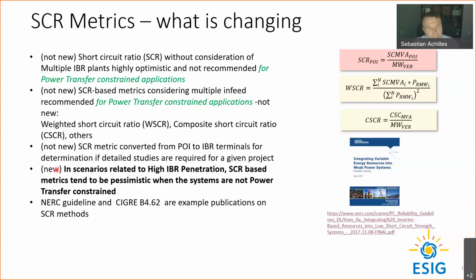Now the aspect that's new, at least to me, is that we're seeing many scenarios more related to high inverter-based resource penetration, like in the previous slides, where power transfer isn't really the challenge. It's more that the system is weak because there are very few synchronous machines close by, even though you're not transferring a lot of power through those weak connections to the grid.